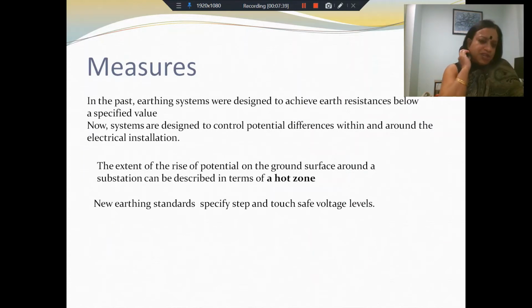Now, how do we deal with this situation? In the past, what we tried to do was reduce the earth resistance value. So we would try to take corrective action whenever the earth resistance value was found to be high. Corrective action was taken in order to bring down the resistive value. Again, we will discuss later how this was done. But there was a specified value, and we had the idea that we needed to bring down the earth resistance below this value. But now we don't care.